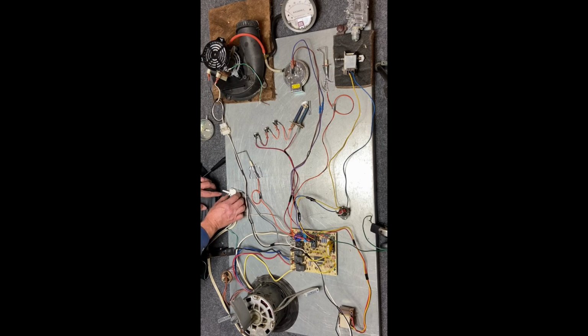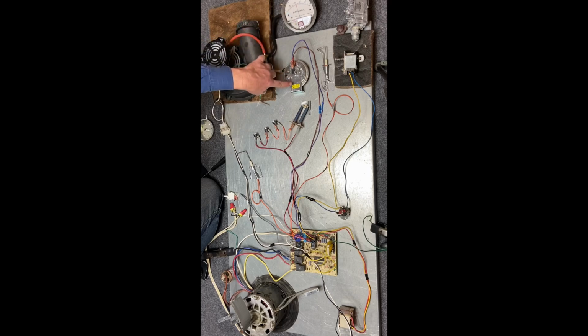Now this switch is broken, so when I push this in, it's going to hold it, which works great for this demonstration, but this switch really would need to be replaced on an actual unit. So here we're going to energize this. Immediately our inducer fan motor comes on. We pull a vacuum. We're pulling more. We need 0.3. We're at 0.4, so that's good.